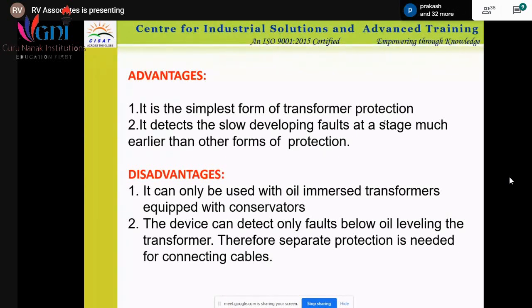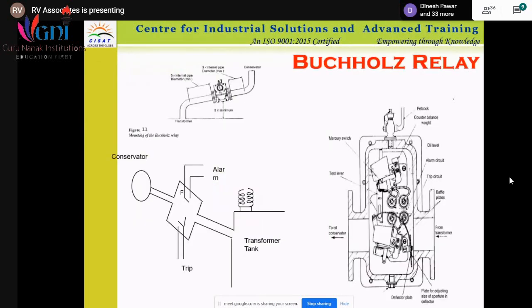What is the disadvantage? The disadvantage is that it can only be used with oil immersed transformers equipped with conservators. It means for distribution transformers or roadside transformers where oil immersed windings are not there, Buchholz relays are not used. Like the present resin cast transformers, you won't use the Buchholz relay. It is only used whenever the winding is oil immersed. This device can detect only faults below the oil level in the transformer. Therefore, separate protection is required for the connecting cables. Okay, this is the disadvantage of the Buchholz relay.